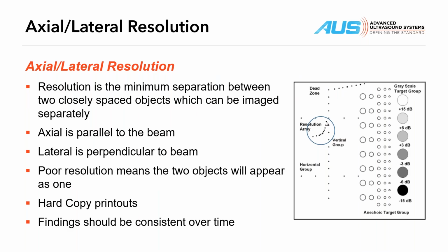And you can compare your axial lateral resolution today to an image you took 3 months ago that you knew was working because they were happy with the image back then. So important part, there's no pass fail limits to this. It's set the system up to get the best image you possibly can and take a picture of that. Again, poor resolution means objects start blurring together. That can be normal for the probe you're using. Let's say you're using an extremely low frequency probe. Maybe that's the best it's ever going to get, but at least you have a printout showing what the best image you could get at that time was. Again, hard copy printouts, and you're looking for degradation over time, which you'll hear me say on all these tests. That's an important factor while looking at phantom resolution.